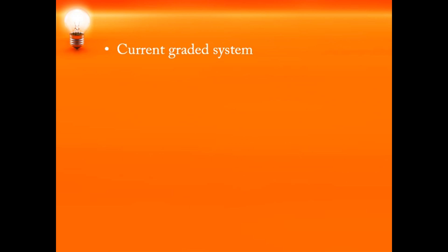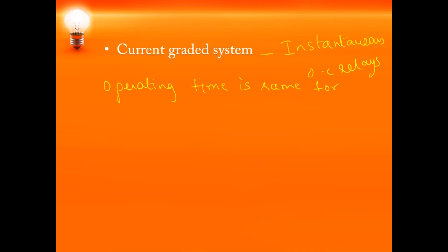Next is the current graded system. Instead of setting the time, in this type of system we set the current — that is the plug setting. In a current graded system, the relays are set to pick up at progressively higher values of current towards the source. The type of relay used here is the instantaneous overcurrent relay, and the operating time is the same for all the circuit breakers — it is not changed.